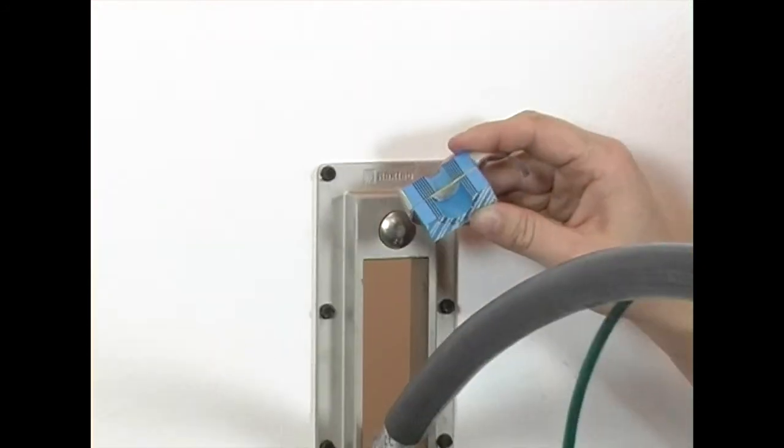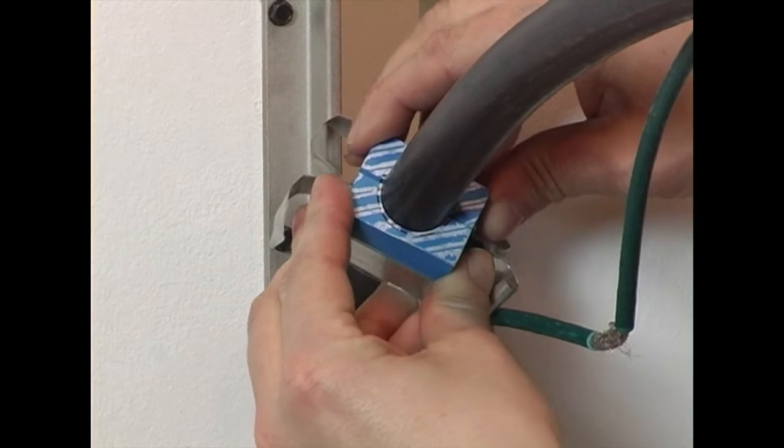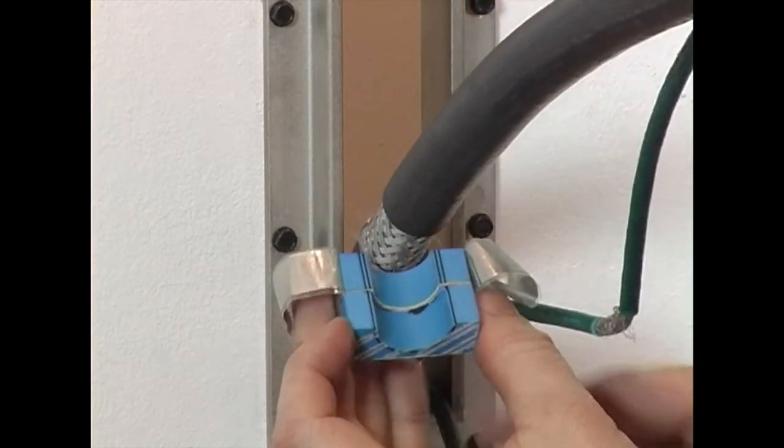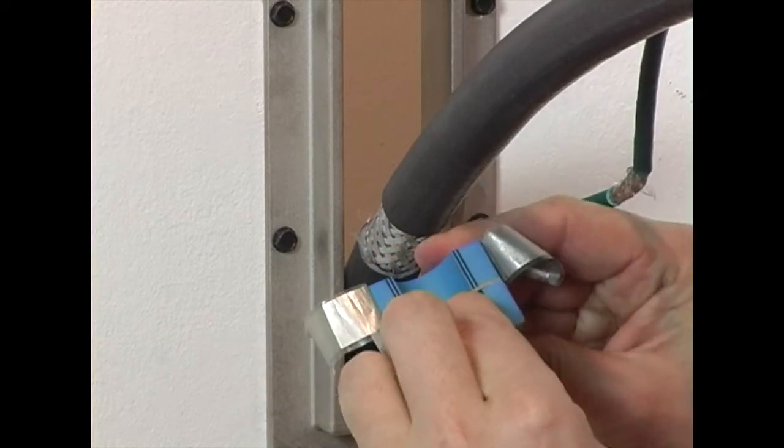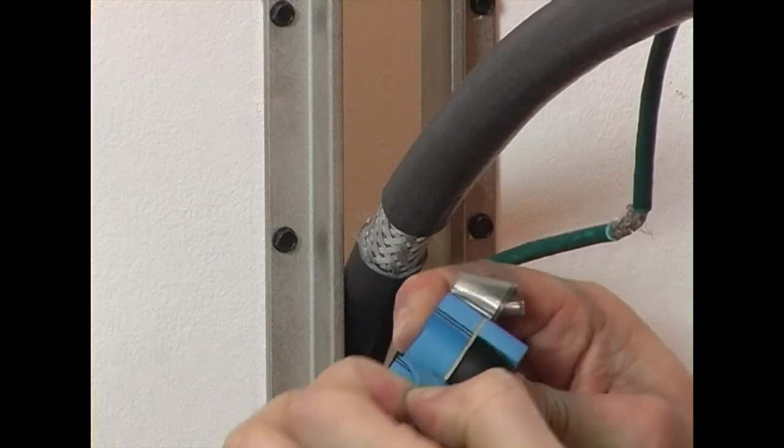It is important that there is a 0.1 to 1mm gap between the module halves when fitting the cable. Peel off layers alternately until the module fits with the appropriate gap. For EMC modules, a smaller gap than that for standard modules is preferable.